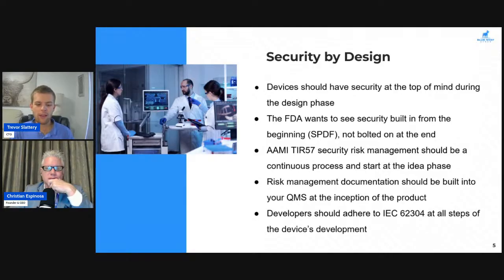A great standard for following this process is IEC 62304, which breaks devices into different safety classifications, class A, B, and C, which is traditionally the European method for classifying devices. FDA goes with class 1, 2, and 3, though in most cases they're going to have a lot of overlap. When we have these different risk profiles, there are different controls and different considerations that we should have at the front of mind, and we should think about building into these products.